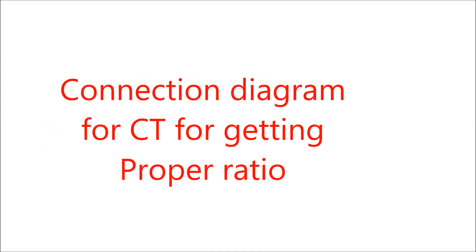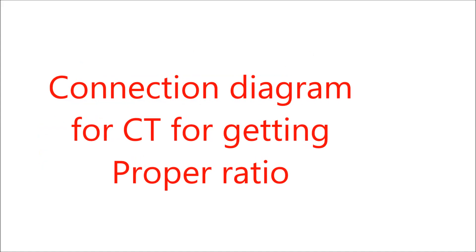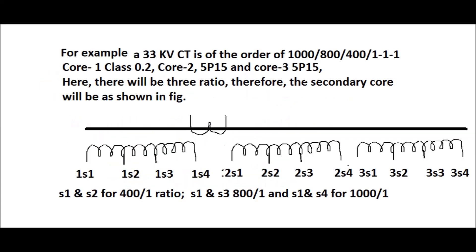Connection diagram for a CT. Here an example has been shown for 33 kV CT connection diagram. The CT ratio is 1000 by 800 by 400 by 1 by 1 by 1. In this case, core 1 is class 0.2, core 2 is 5P15 and core 3 is 5P15. Here core 1 is used for metering purpose.